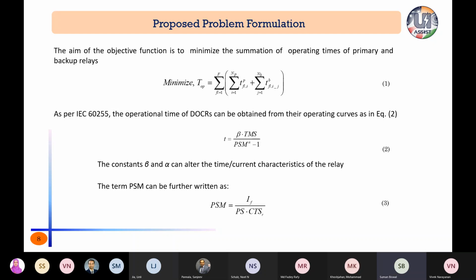To ensure the coordination of the relays, the time of operation can be expressed as in equation 2. That is beta times TMS, the whole divided by PSM to the power alpha minus 1. So beta and alpha govern the characteristics of the relay. For example, for beta equals 0.14 and alpha equals 0.02, that gives us the inverse characteristics of the relay, the normal inverse. If beta and alpha change, the characteristics will change. For very inverse or extreme inverse, the other characteristics are there, and for them beta and alpha vary.